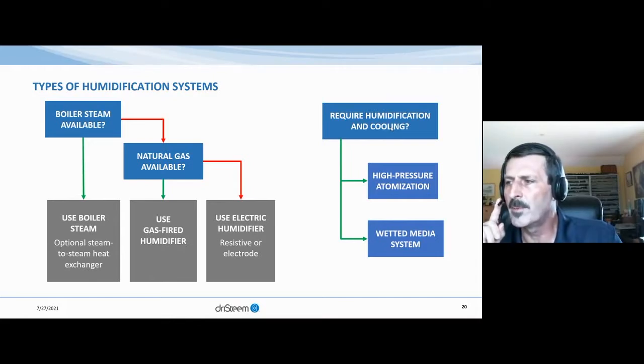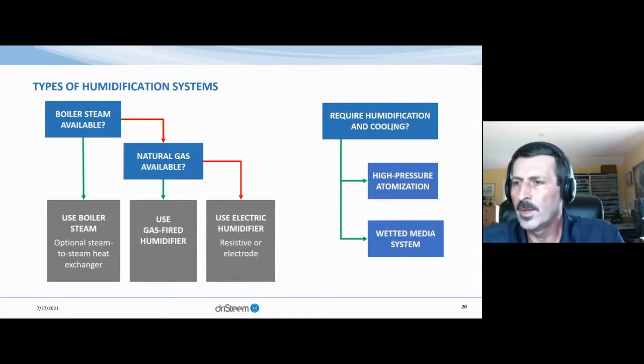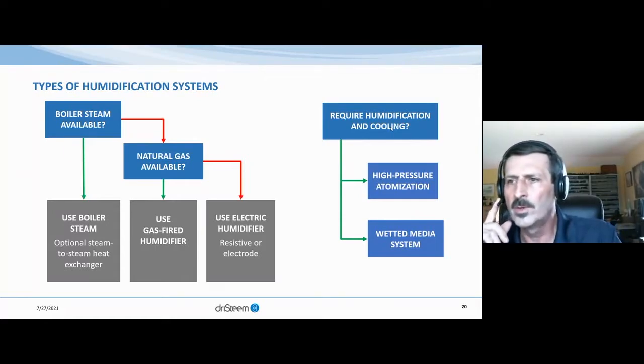And of course, electricity is generally available and may be your choice, particularly for small loads or in-room applications. Note that where higher accuracy is required, a resistive or heater element unit will likely be significantly more accurate than, say, an electrode unit. Moving to the right, we see some adiabatic system choices. These are attractive where cooling is a desirable option. And remember, many industrial facilities have excess process heat. Adiabatic solutions may also be preferred where hot, dry external conditions exist.